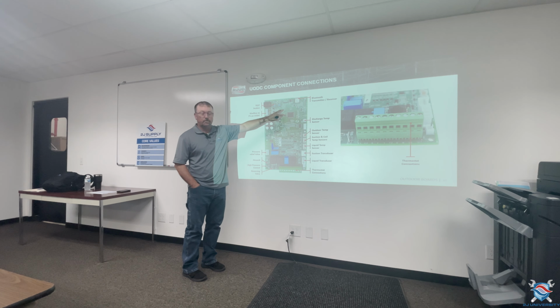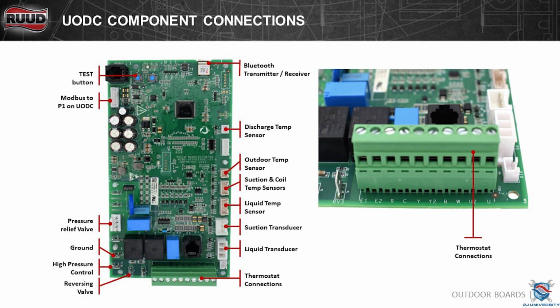So let's walk around this board a little bit. We got our Bluetooth transmitter. Once again, we have our discharge temperature sensor, our outdoor temperature sensor, suction and coil temperature sensor, and liquid temperature sensor. Something else that is a little newer to this is the suction transducer and liquid transducer. Got your thermostat connections along the bottom. Got your reversing valve hookup here. High pressure control. Pressure relief valve. Your Modbus connection. And then your test button. If you're in a 24 volt application, you can use this test button and send it into charging mode through here. If you're in an EcoNet, you're going to send it into charging mode through the EcoNet.